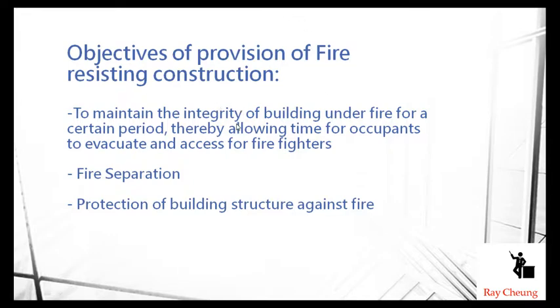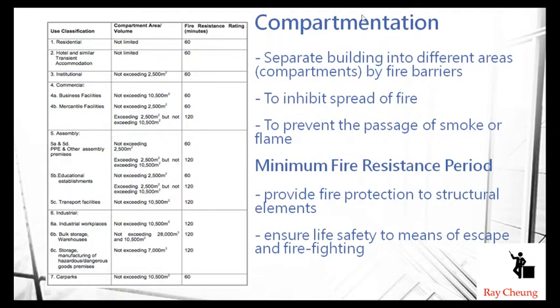Normally we need to maintain the integrity of the building during fire. That means in case of fire, the building will not collapse and people will have sufficient time to escape from the building. This means we need fire separation and protection of the building against fire. The first requirement is compartmentation — the area or volume of the building should not be too large.